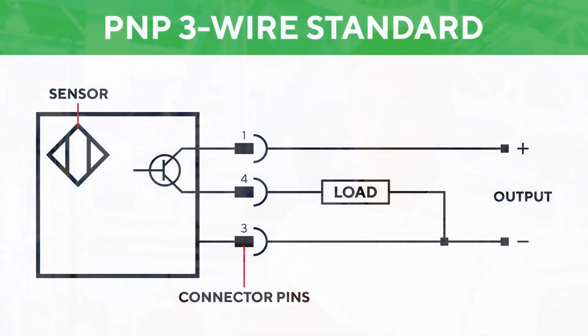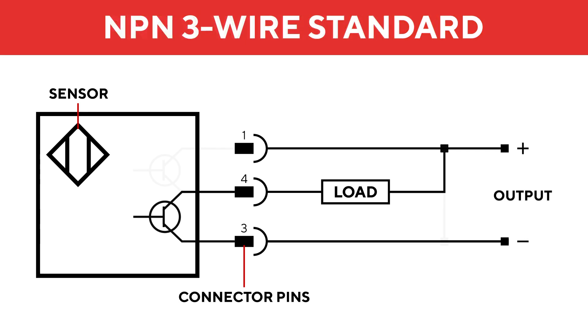An easy way to remember how each sensor output works is to look at the first letter. When we look at PNP, the first letter is P meaning positive, so that sensor is actually pulling its signal from the positive load of the sensor. And with NPN, the first letter is N meaning we're pulling a negative signal back to your PLC.